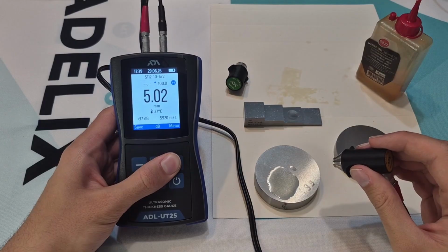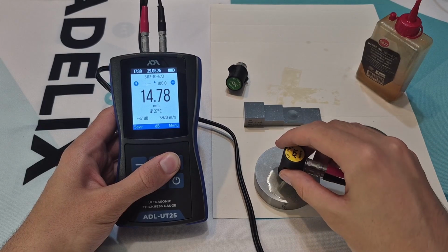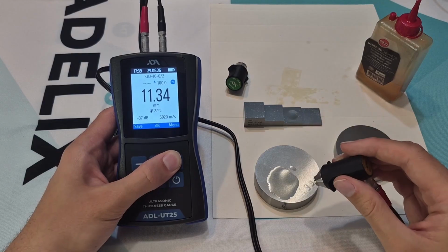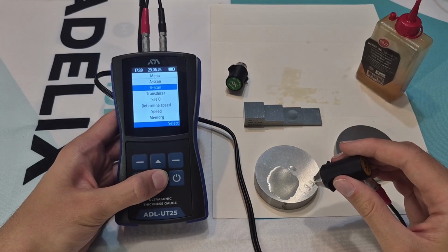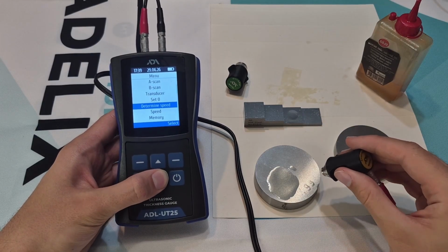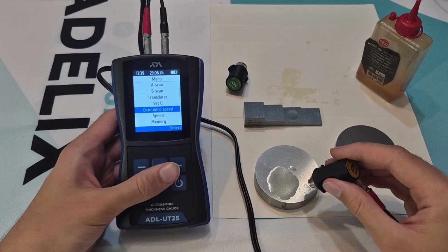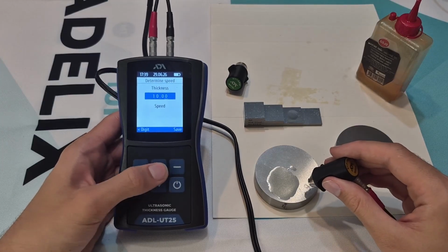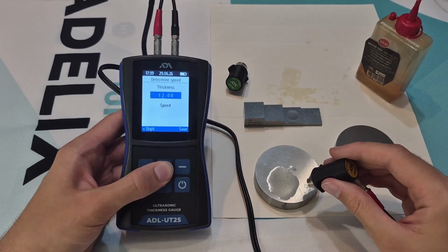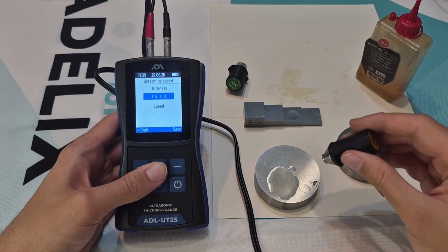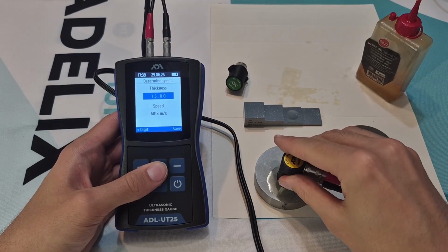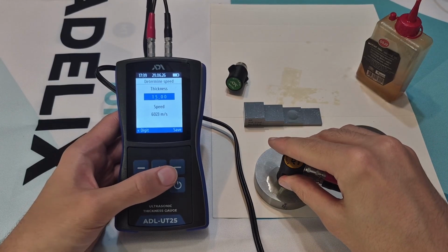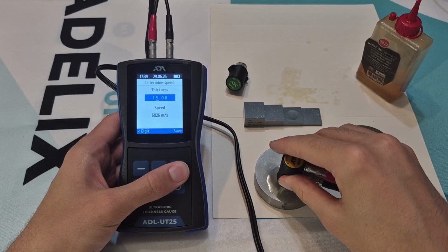If the ultrasonic velocity in the material is unknown, but the thickness of the sample is known, the device can automatically determine the ultrasonic propagation velocity. For example, for this 15 mm thick sample, the device determined a velocity of about 6,025 meters per second. After that, measurements of other parts made of the same material can be taken. For example, 10 mm thick.